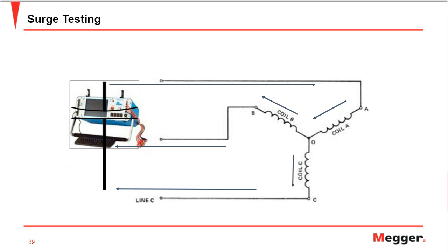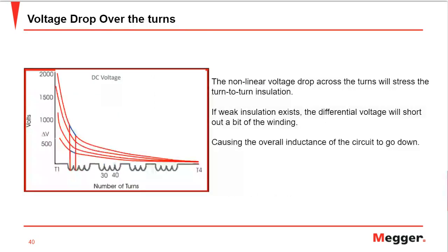displaced by this capacitor. And the measurement is of course taken at the terminal voltage conductors of the motor, and it is with respect to time, which gives us the surge waveform. And we'll see further ahead that those waveforms are damped oscillations. Excuse me. And we'll see the voltage drop over the turns in the next slide, which also helps us understand why the rise time of that voltage spike is important while doing a surge test.